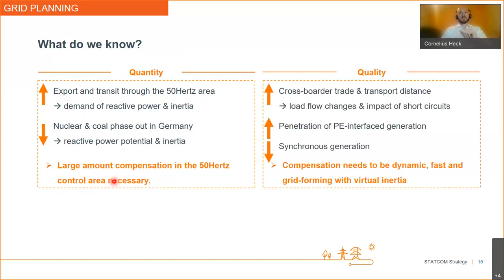And this will be combined with a lot higher cross-border trades between European countries, and thus giving the transport distance also an increase. And this will lead to much higher load flow fluctuations. And if you remember the slide that Florian has shown already today, you see during load flow changes, voltage changes of up to 5 to 6 kilovolt. And this will increase dramatically over the future. And due to the increase of transport distance, the impact of short circuits will also increase. At the same time, we're looking at an increase of the penetration of power electronic interface generation and a reduction of synchronous generation. And that's why we need compensation that is dynamic, fast, grid forming with virtual inertia.